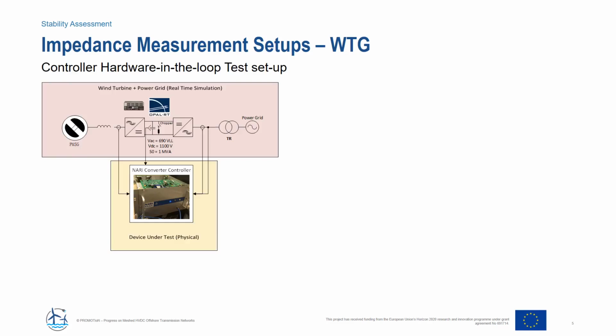So the measurement for the wind turbine generator impedance is shown below. As we perform both, to the left you see a controller hardware in the loop test setup. Here you see the real controller replica from the OEM, and to the top you see the wind turbine primary components and the power grid implemented in the real-time digital simulators. This is the controller hardware in the loop testing.